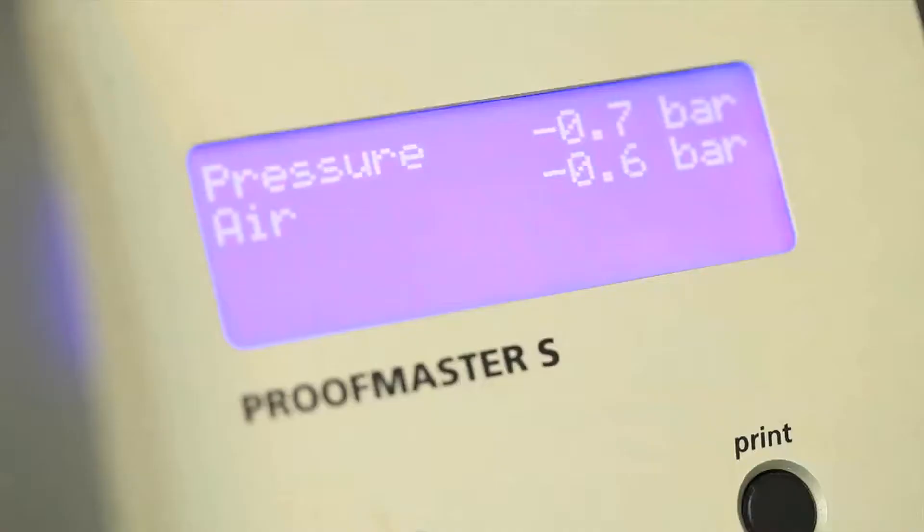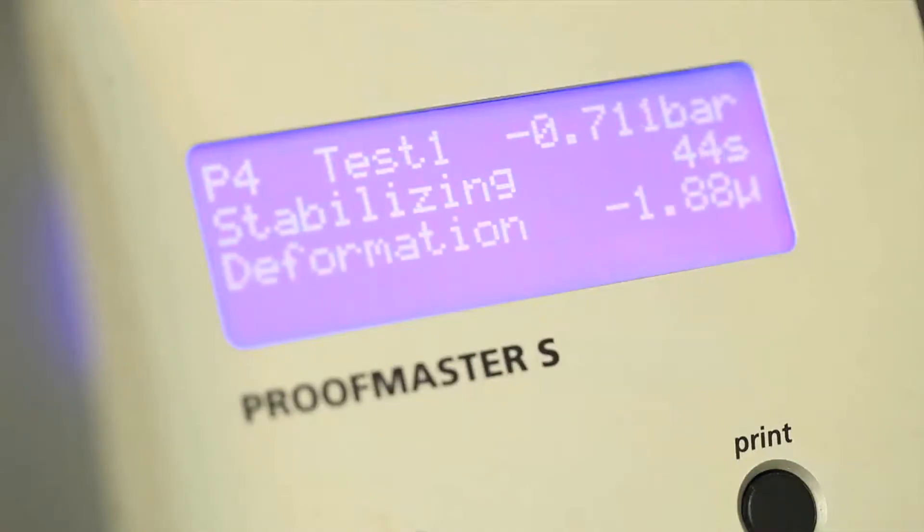The machine itself verifies the water resistance using a two-step process consisting of vacuum and positive pressure. While what happens inside the machine may be thought of as complicated, the process of running the test is actually quite simple.